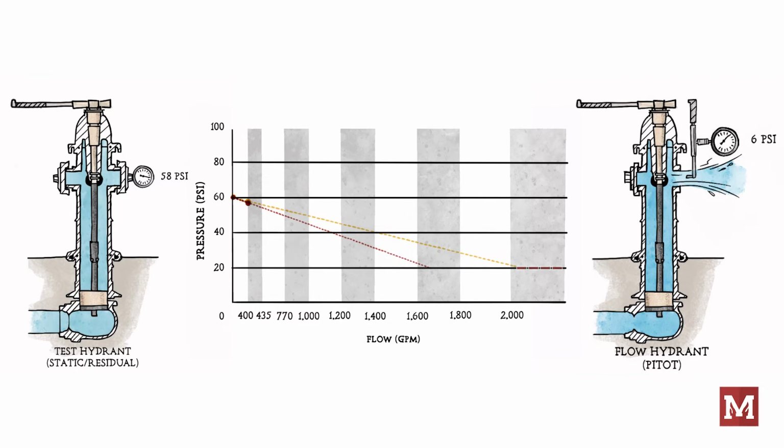Well, we still have uncertainty. A calibrated gauge can still be off by some allowable margin. Our measurements are really not perfect. They're still just a test with measurements that estimate a supply. The problem with flowing too little water is that any small deviation, whether it's our error or an error in the equipment or just the natural tolerances that go into a test, is compounded when we later extrapolate that data far beyond our measurement range.